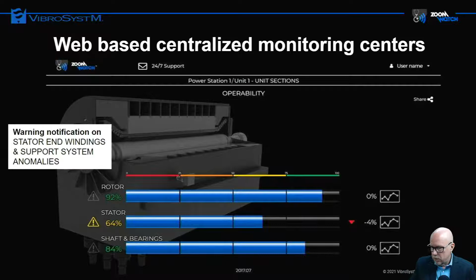Severity levels are the actual severity for each particular phenomenon on the asset. We have an example here for a turbo unit, where we're monitoring the stator core and frame attachment system, the stator bar wedging system, and the end windings and support system. The stator core deterioration on this unit was not monitored, nor was the stator bar deterioration.